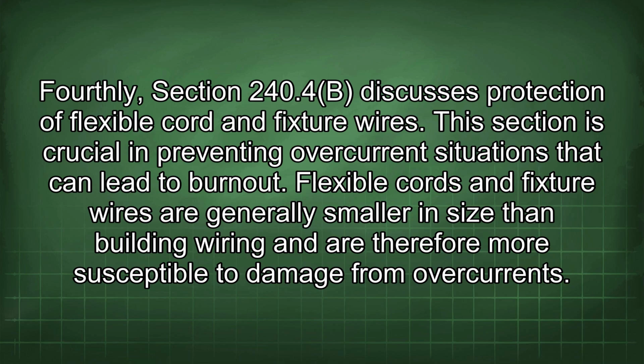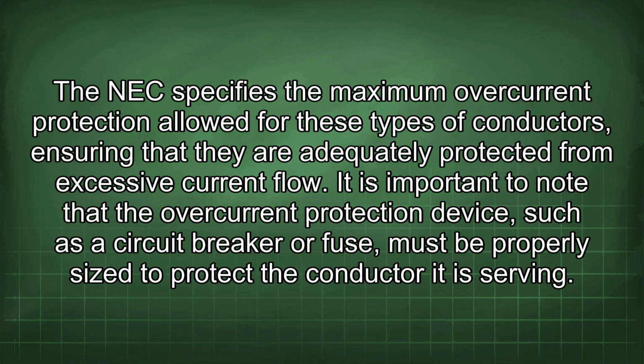Fourthly, Section 240.4(B) discusses protection of flexible cord and fixture wires. This section is crucial in preventing overcurrent situations that can lead to burnout. Flexible cords and fixture wires are generally smaller in size than building wiring and are therefore more susceptible to damage from overcurrents. The NEC specifies the maximum overcurrent protection allowed for these types of conductors, ensuring that they are adequately protected from excessive current flow. It is important to note that the overcurrent protection device, such as the circuit breaker or fuse, must be properly sized to protect the conductor it is serving.